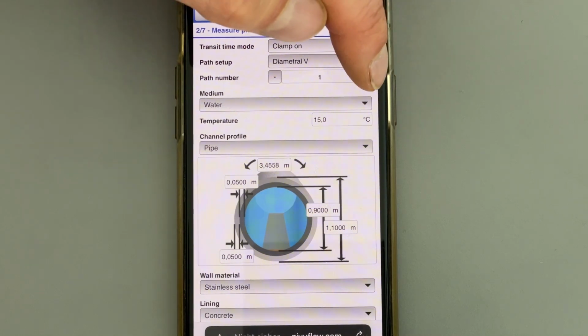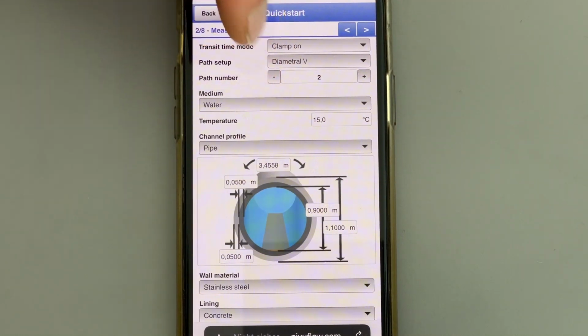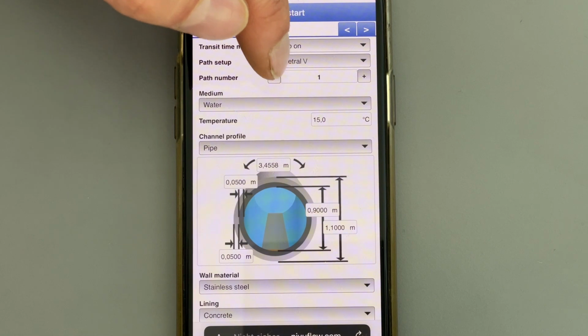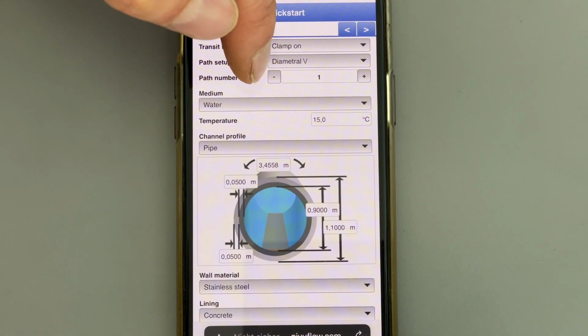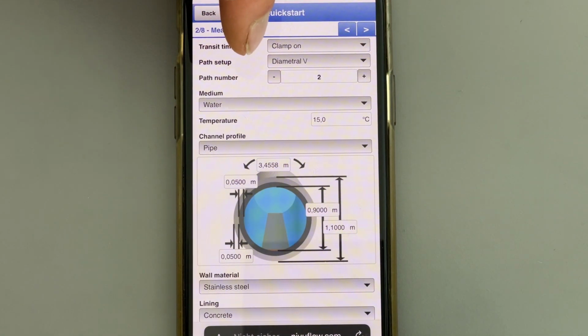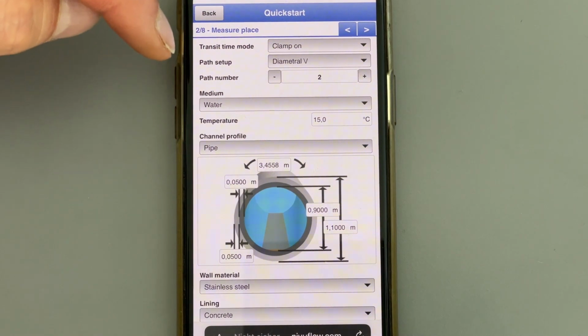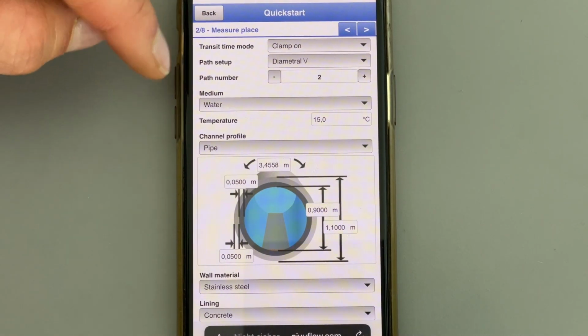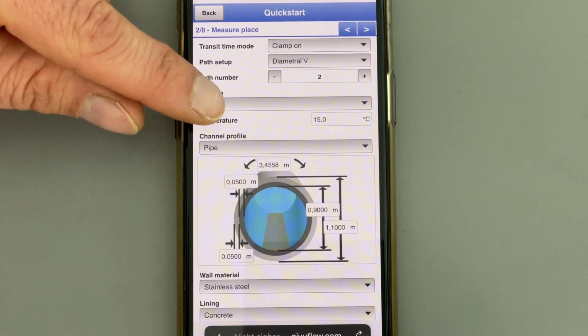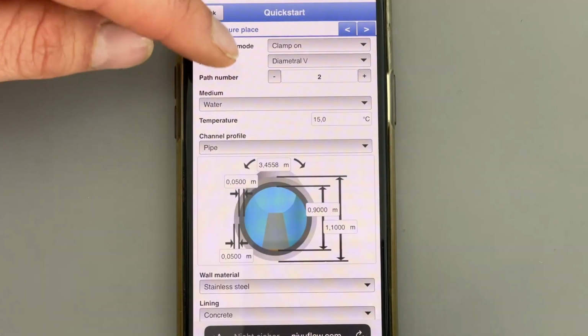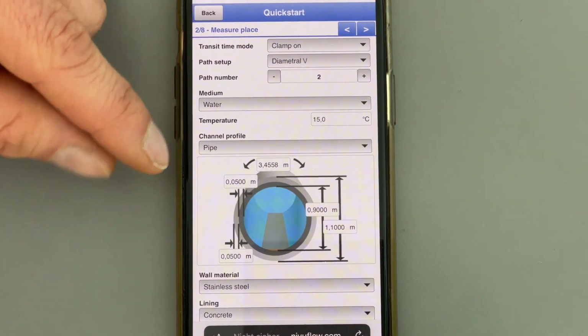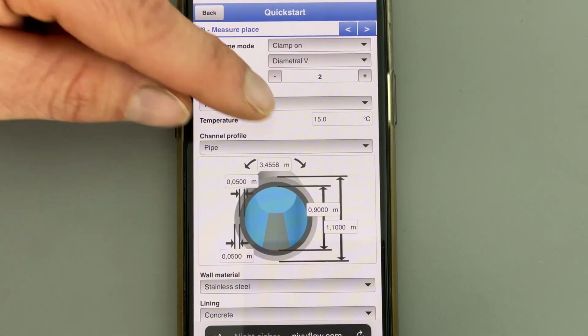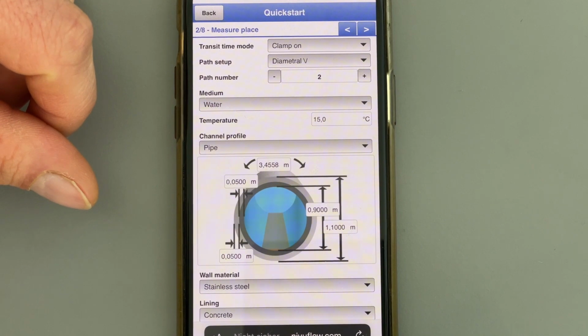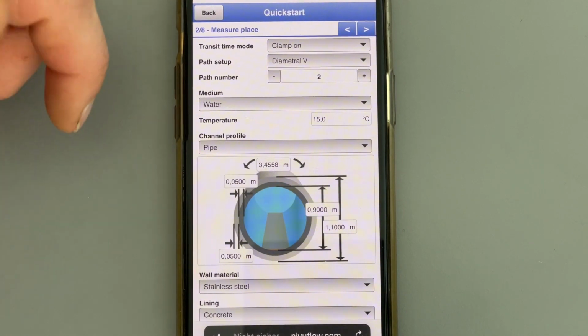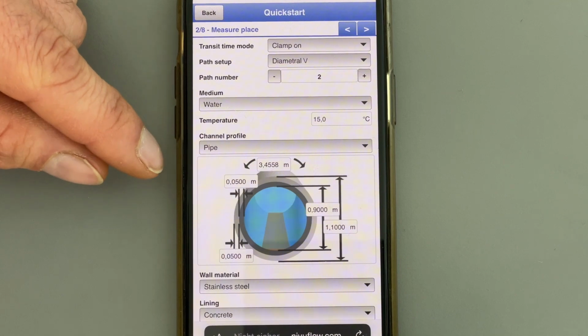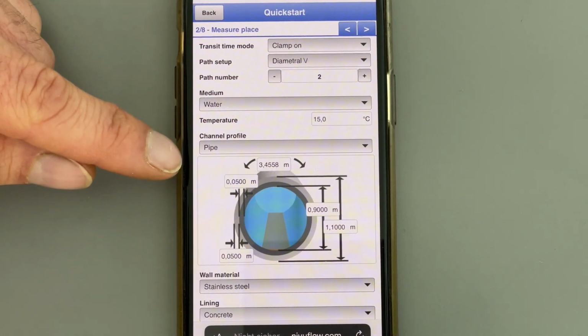The path number in this case means the number of sensor pairs you have connected, usually always 1, but optionally you could have 2 sensor pairs on the same pipe for a more reliable and accurate reading of the flow. The medium, you can choose water, which is the standard one, but you could also define your own medium. The temperature is the temperature of the water inside, or if you have the option to measure it, that's also good. So you type in the temperature here.